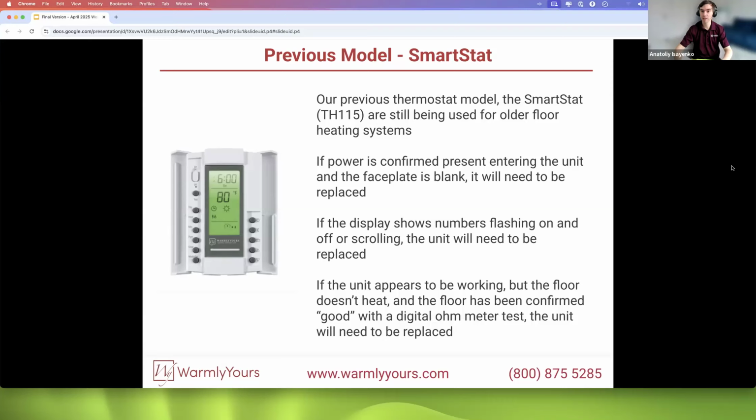To answer your question, if I fully understood, yes, if you have a 120 volt floor heating system but an electrician by mistake supplied 240 volts to it, that will eventually overheat and damage the system, unless it was just hooked up and turned on for a second or two. Right, Scott? Yes. That's a great question, Ken.